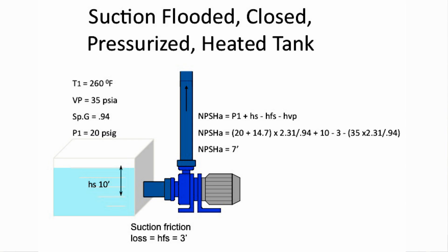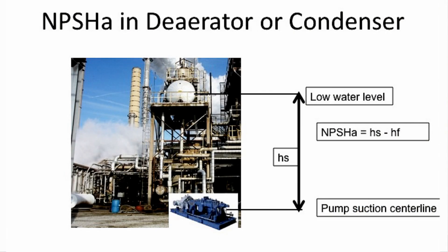Again, looking at the same system — everything is the same except the temperature goes up to 260 degrees Fahrenheit, which is the boiling temperature of 20 PSIG water. So the water is boiling, and therefore the 20 PSIG suction pressure is canceled out by the vapor pressure. The NPSHA is only the static height minus friction. This is a very common application in boiler feed water pumps, where the suction is from a deaerator, which is a boiling vessel. Another would be a condenser, where the liquid is condensing. In these cases, the NPSH is only the static height minus the friction.